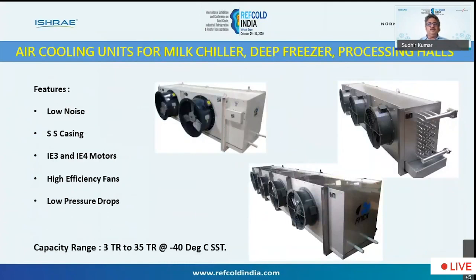Next comes the air cooling units. Olden day refrigeration plants used to have air cooling units floor mounted, having a blower and having a ducting system. But now the latest air cooling units are all with stainless steel, aluminum fins and more energy efficient, using again IE3 and IE4 motors and all low noise, and also it is hygienic nowadays because all the dairy projects are all HACCP approved. So you need to have hygienic coolers where you can have an SS casing or a powder coated casing.